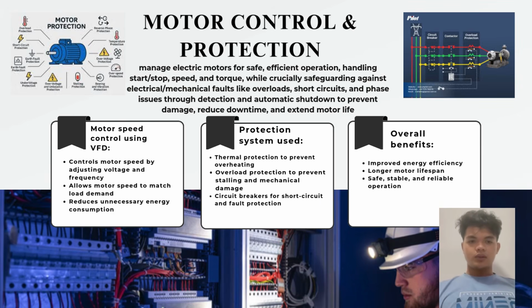The VFD controls motor speed by adjusting the voltage and frequency, allowing the motor speed to match the load demand. This helps reduce energy wastage and improve efficiency. For protection, thermal protection prevents overheating, overload protection avoids stalling and mechanical damage, and circuit breakers protect against short circuit. Overall, these systems improve energy efficiency, motor lifespan, and operational safety.